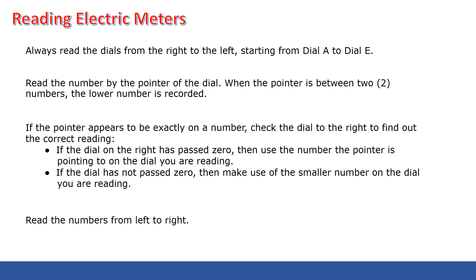When reading an electric meter, always read the dials from right to left, starting from dial A to dial E. The second step: read the number indicated by the pointer. When the pointer is between two numbers, the lower number is recorded. If the pointer appears to be exactly on a number, check the dial to the right. If that dial has passed zero, use the number the pointer is on; if not, use the smaller number.